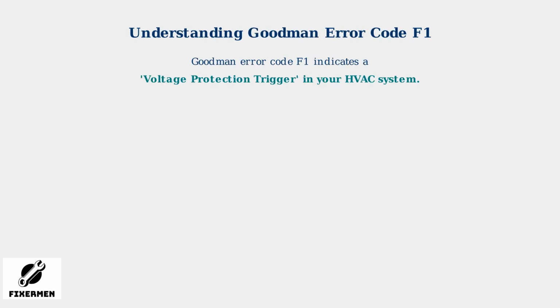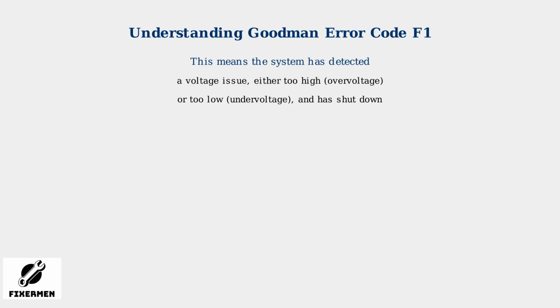Goodman Error Code F1 indicates a voltage protection trigger in your HVAC system. This means the system has detected a voltage issue, either too high (over voltage) or too low (under voltage), and has shut down to prevent damage to components like the blower motor or compressor. This safety mechanism is designed to protect your HVAC unit from power surges, wiring problems, or transformer failures.